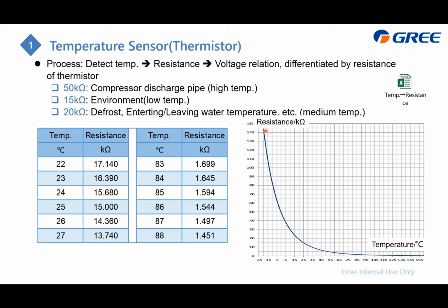And also you can find it. This is the relation between the resistance value and the temperature sensor. We always use this part to check the resistance and also the temperature, which means it is more sensitive, right? So this is the reason why we need to have 3 types of sensors, because the sensitivity is different. And why we call it 15K ohm or 20K ohm is based on when the temperature is 25 degrees and the detected resistance value is 15, just like this is the 15K ohm sensor.